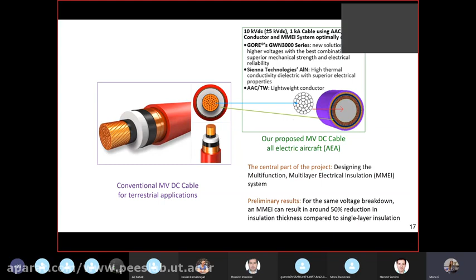However, the main goal is changing the insulation. For the terrestrial cable, we have only one layer of insulation. Here, what we are doing is proposing a multifunctional, multi-layer electric insulation. We could show that for the same voltage breakdown, this multi-layer insulation can result in around 50% reduction in insulation thickness, meaning a reduction in the weight of the insulation.